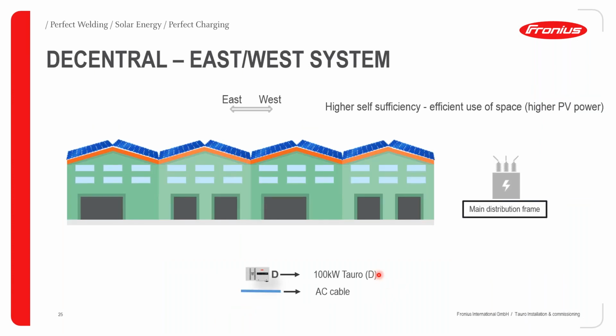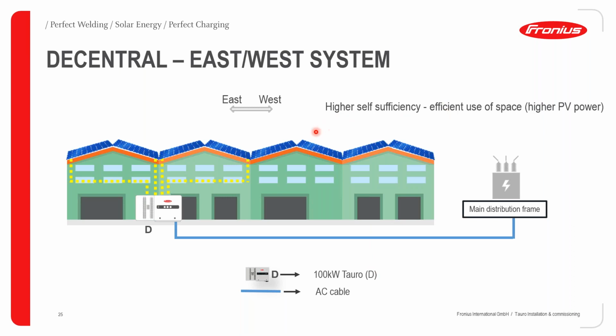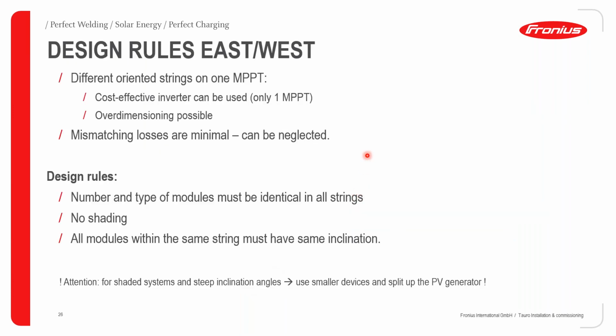In another installation, a variation of a decentral system, we can also talk about bringing your DC cables directly to the inverter. Then from the inverter, you go into the feeding point with much larger or thicker AC cables. But what are the design rules for east-west orientation? Here are some hints we can give you.